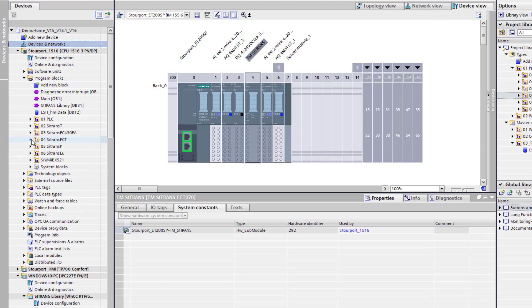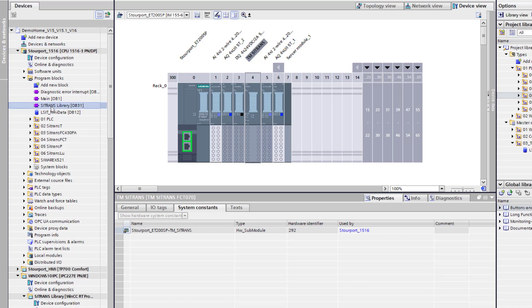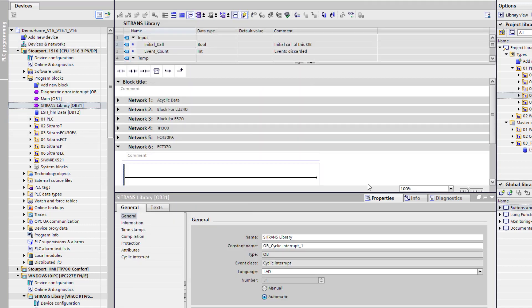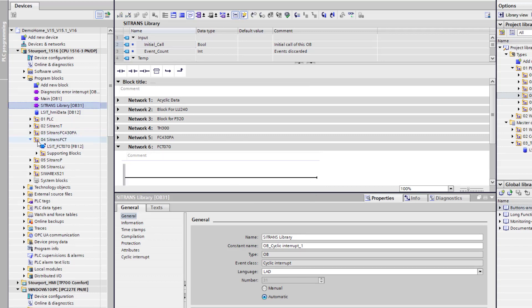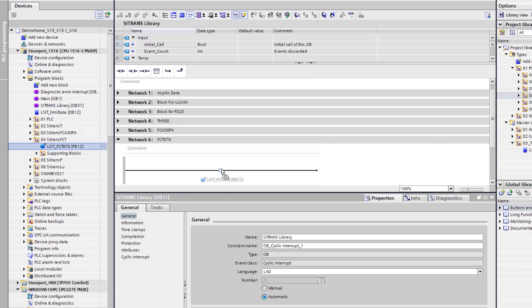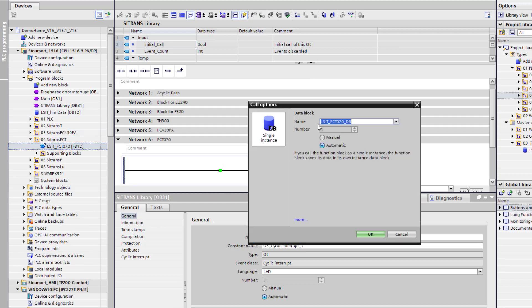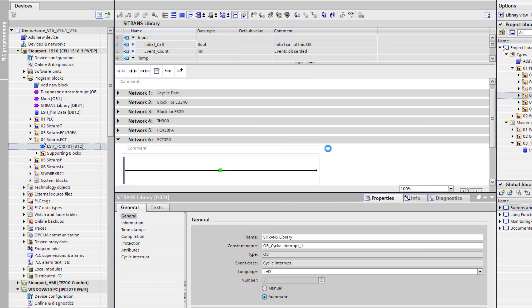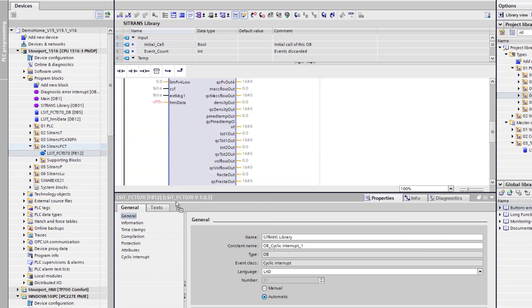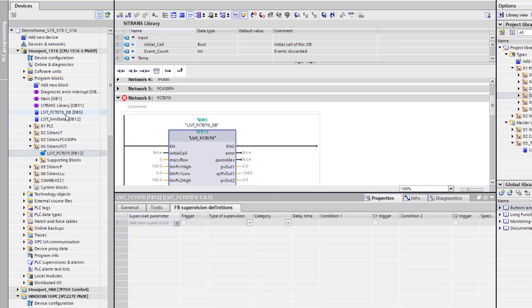So the next thing we need to do is to bring that into an interrupt. And it needs to be a time interrupt. And in this instance we are using OB31. So OB31 is there. And all I need to do now is to drag my function block in. So here it is automatically generating the data block number. So if I click on OK, data block 5. And you can see that has been generated.